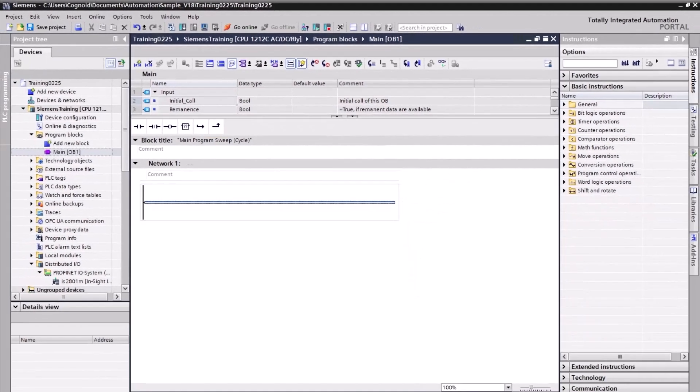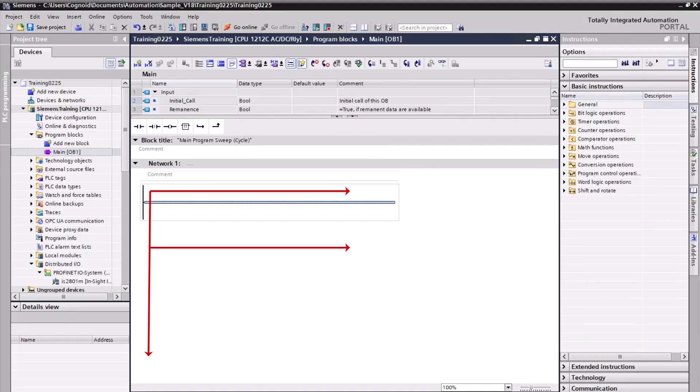Rungs and networks are executed from top to bottom and left to right. The first instruction in the first rung of the first network is processed first. All instructions of that rung are then processed, followed by all other rungs of the first network. The next network is processed only after all rungs have first been run.